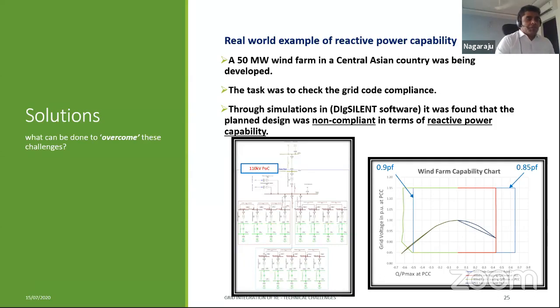But when they went to the grid operator, the grid operator told them that they need to show that the 50 megawatt wind farm is compliant with all the grid code requirements. So they came to us asking to study all this. One of the issues we found is that with the current design, the wind farm cannot meet the reactive power requirement.